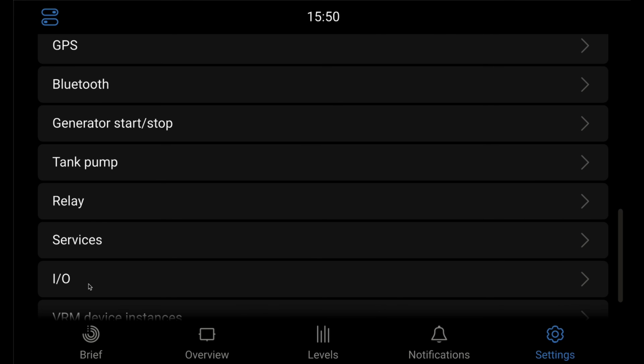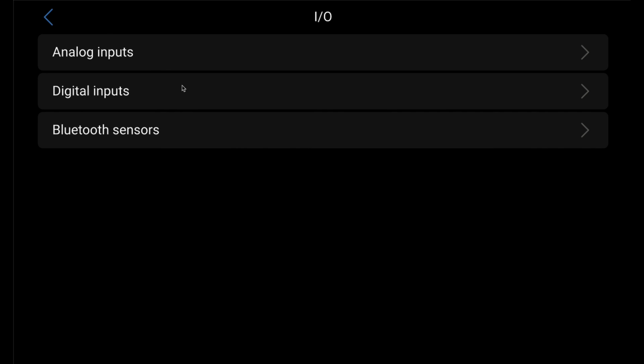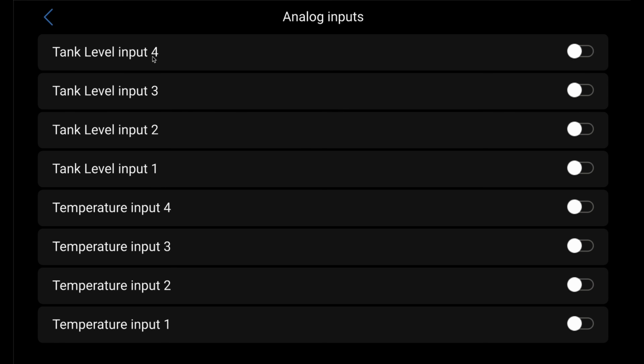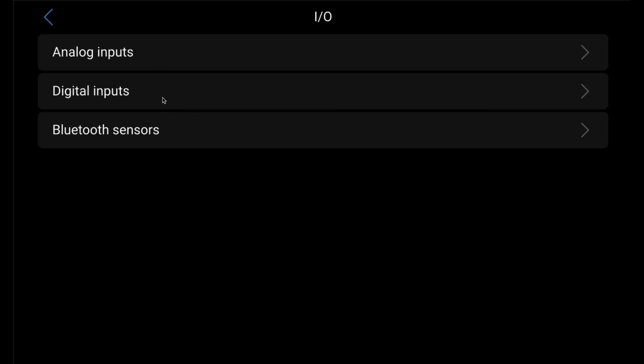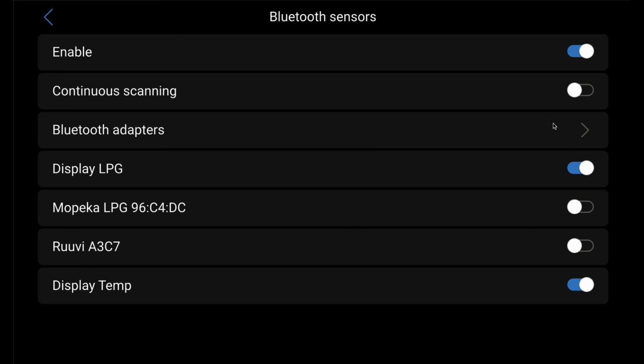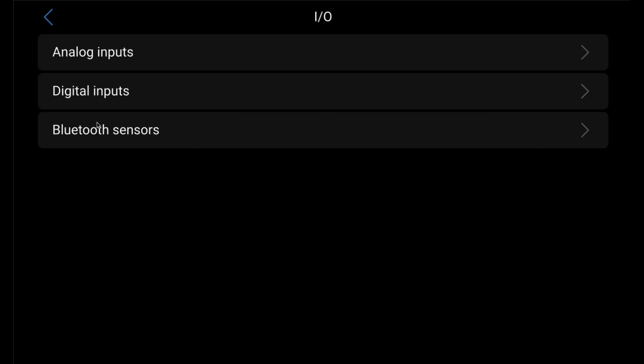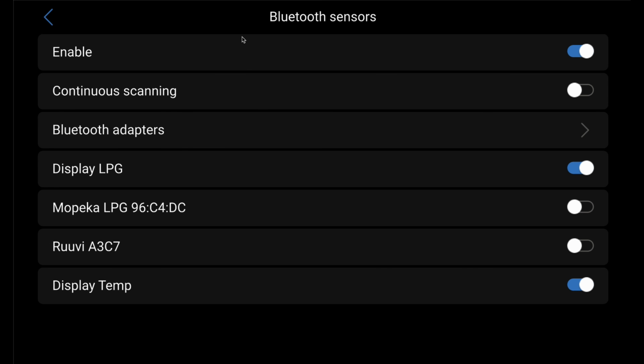Below the services tab, we have this I/O tab. Inside of this I/O tab, we can turn on and off different inputs on the Cerbo. These include the analog inputs like tank level and temperature levels, as well as the digital inputs and the Bluetooth sensor inputs. And this is where we'll also add or remove those specific devices. As you can see here in the case of Bluetooth sensors, once I go into this tab and the Cerbo detects that there's an available sensor, I'll have it here with a closed toggle. Once I turn that toggle on, this device will now show up in our device list and will be able to be programmed and modified.